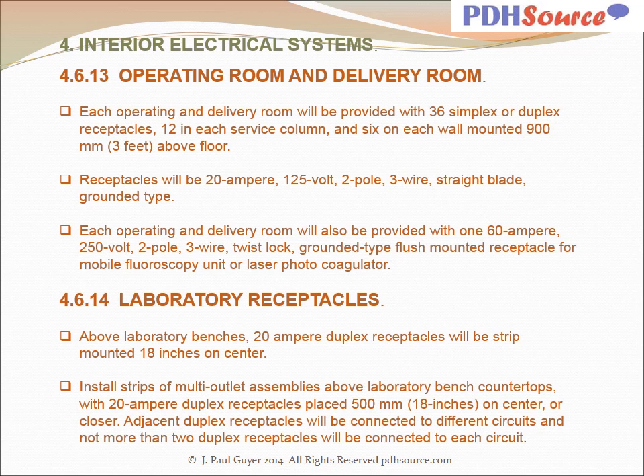For laboratory receptacles, above laboratory benches, 20 amp duplex receptacles will be strip mounted 18 inches on center. Install strips of multi-outlet assemblies above laboratory bench countertops with 20 amp duplex receptacles placed 18 inches on center or closer. Adjacent duplex receptacles will be connected to different circuits, and not more than 2 duplex receptacles will be connected to each circuit.